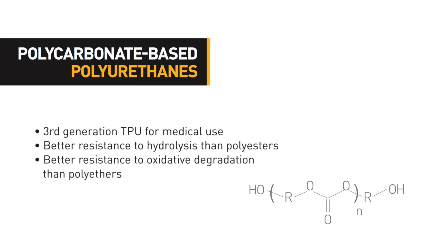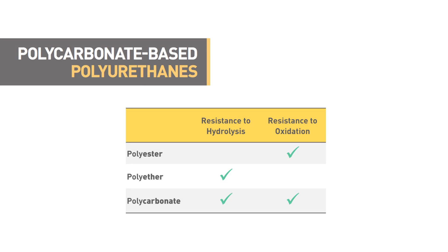The third generation of urethanes for medical devices is the polycarbonate-based polyurethanes. Polycarbonates have the best characteristics of both the esters and the ethers: better resistance to hydrolysis than the polyesters, and better resistance to oxidative degradation than the polyethers. These desirable characteristics make them a popular choice for use in medical devices.